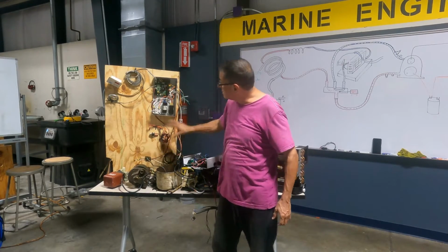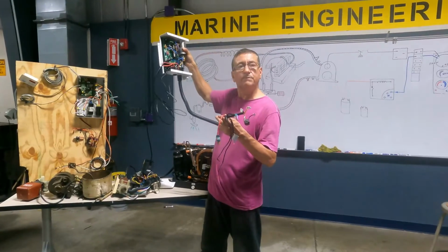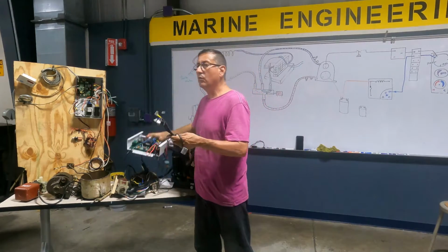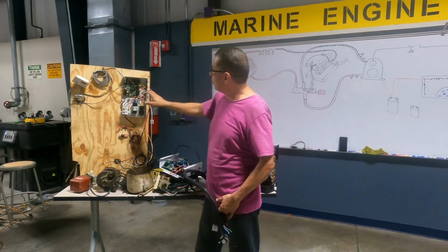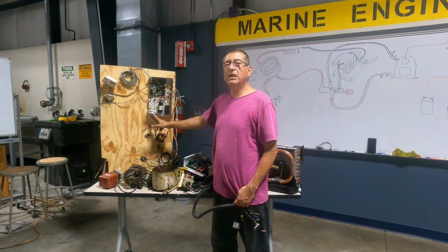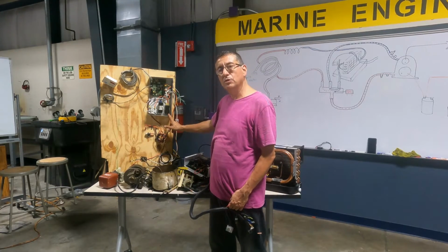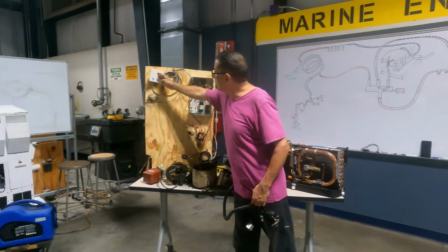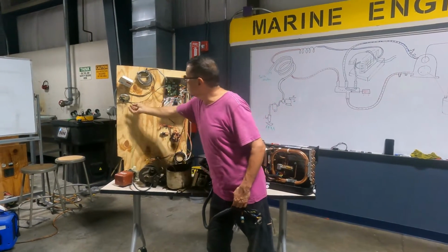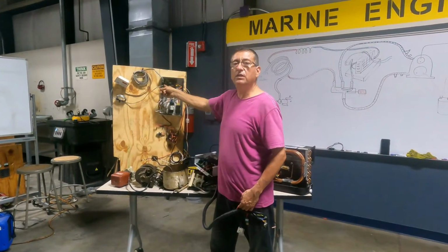If you see, this harness is exactly the same. It's exactly the same as this. You have the same components. We are going to repeat the components. One component is the main circuit board. The other component is the system relay. The other one is the run capacitor and start capacitor. And the thermostat with the cable to connect the thermostat on the circuit board. And the sensor for the temperature in front of the air filter, connected in the circuit board.